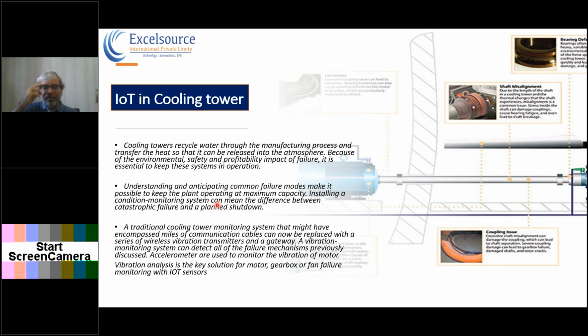So how can we optimize this energy when it is not experiencing the same wet bulb temperature during the rest of the year? Like in winter, the wet bulb temperature is quite low. Even at the peak of the summer, where the humidity is low, the wet bulb temperature is low. So how can we optimize this? IoT is going to help in the optimization of the energy during the off-peak hours, or the off-peak time of the year.